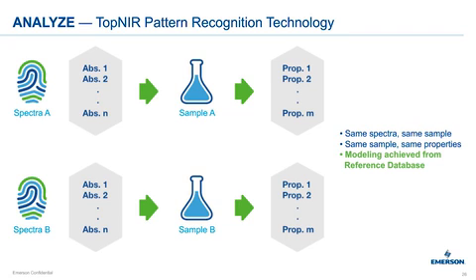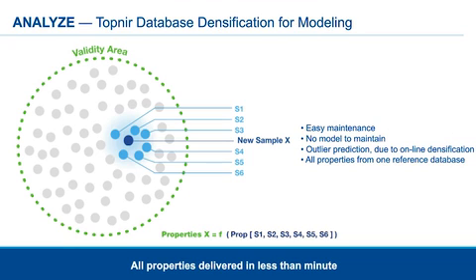So like any other NIR, near-infrared analyzer, there is a light source in the infrared light region, a measurement cell with a defined path length, and a detector. The initial light signal is attenuated in the sample cell and read in the detector. The FTIR then performs a mathematical operation on the data to enrich the information as opposed to normal NIR.